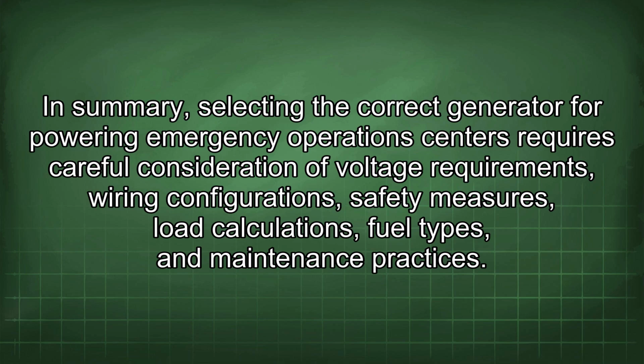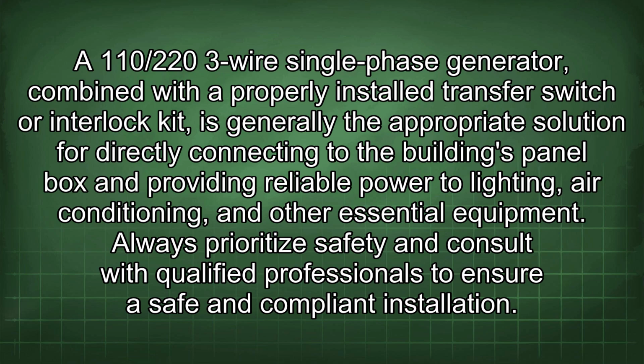In summary, selecting the correct generator for powering emergency operations centers requires careful consideration of voltage requirements, wiring configurations, safety measures, load calculations, fuel types, and maintenance practices. A 110/220 three-wire single-phase generator combined with a properly installed transfer switch or interlock kit is generally the appropriate solution for directly connecting to the building's panel box and providing reliable power to lighting, air conditioning, and other essential equipment. Always prioritize safety and consult with qualified professionals to ensure safe and compliant installation.